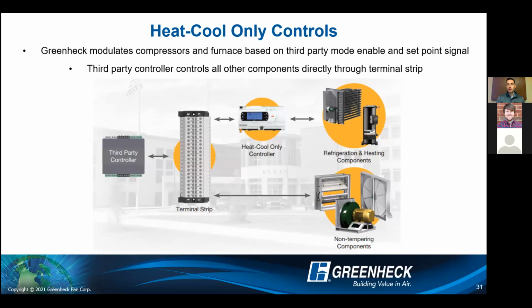Moving on to heat cool only control. So obviously not necessarily full factory controls, and where we generally see this being very common is in school or education type situations. So a lot of the times we see school districts or maybe counties that prefer their third-party controller or their own controls logic that is handling all the equipment on the building. So what we do with this is we have a terminal strip that we allow that third-party controller to be tied into. And then from that terminal strip, there's two different things that happen.